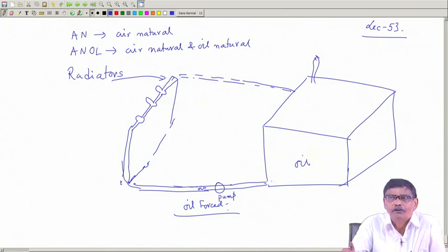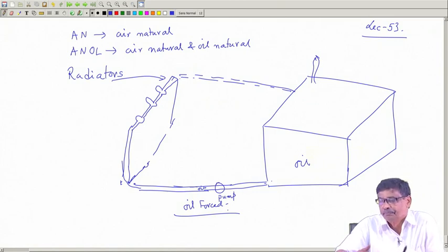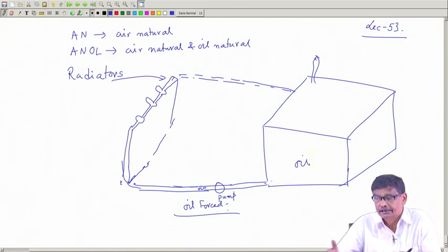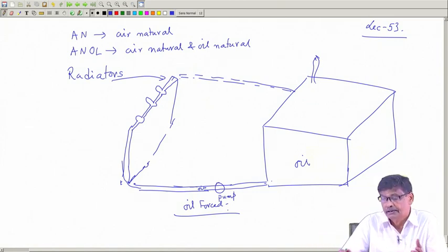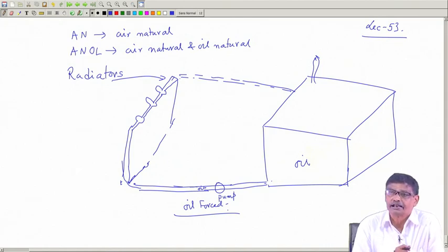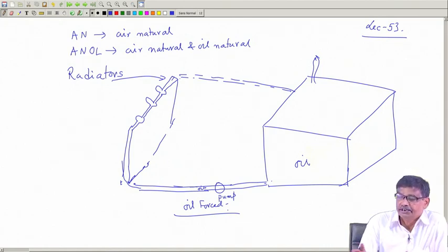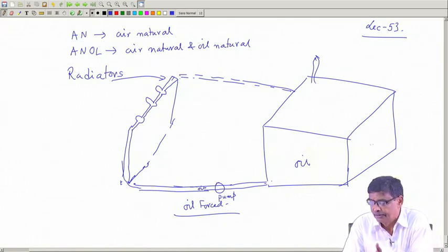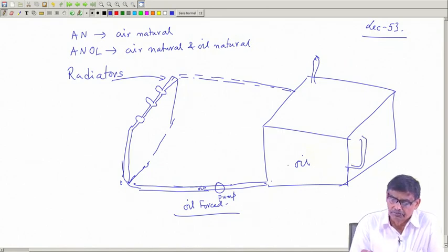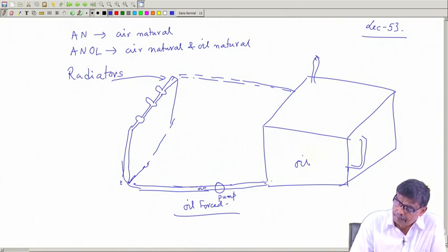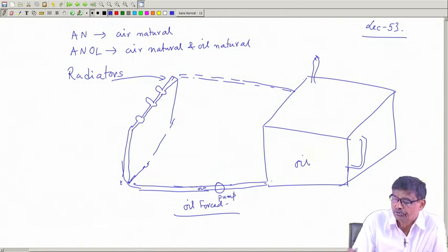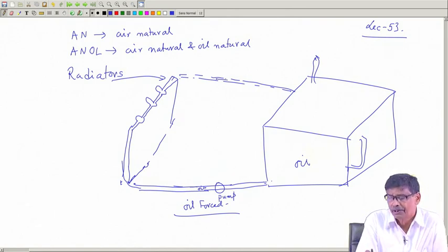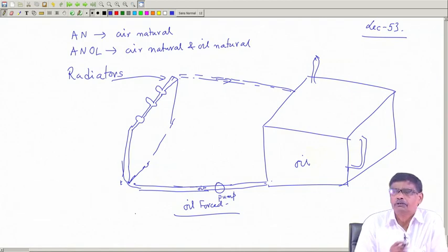Therefore, since you have gone for a higher kVA rating, the size of the transformer has increased, and you must have an elaborate arrangement to artificially increase the surface area of cooling. Heat will be radiated not only from the usual tank here, maybe tubes also connected with natural circulation of the oil, but you also force the oil to move through the radiators to make a closed path, and oil will be circulating.